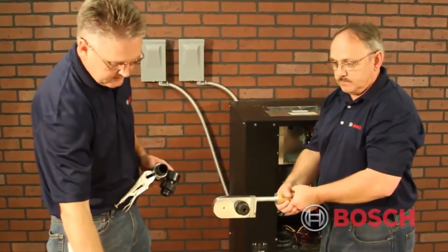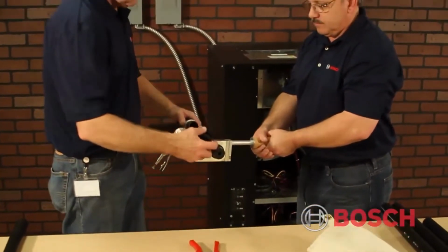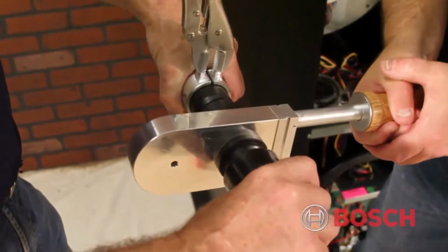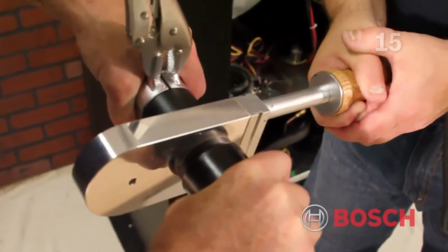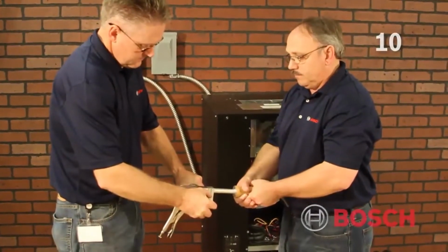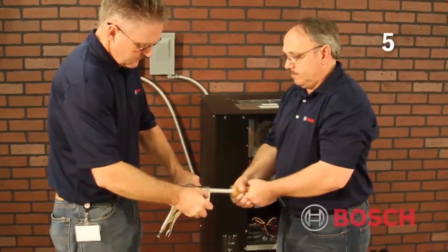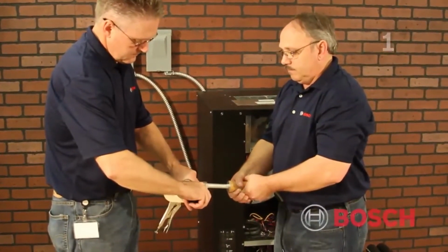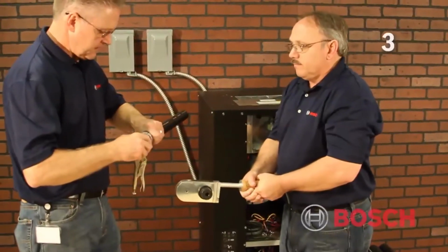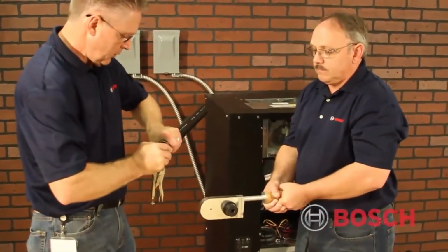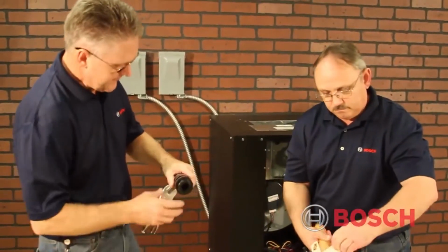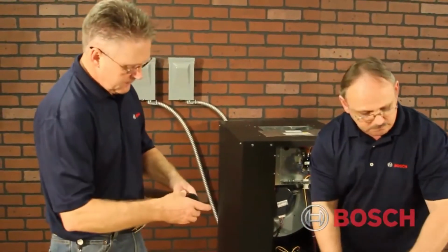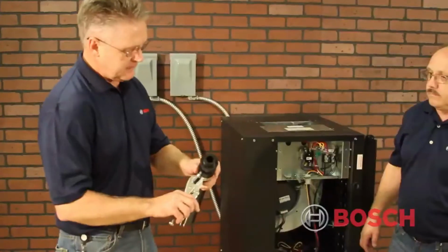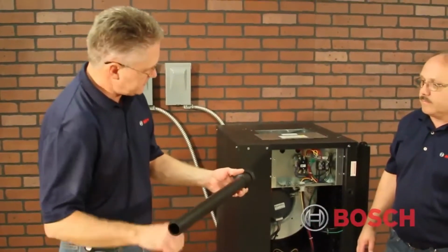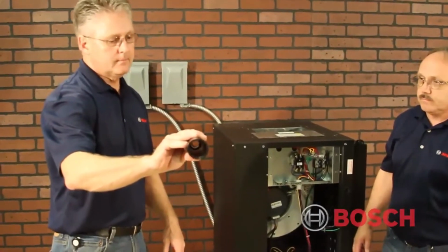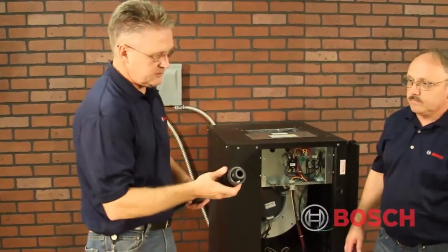This is our timer. I've got 3 seconds to put it on, and then I'm going to hold it for about 60 seconds to make sure that it sets up, and we're not going to play with it or anything like that for about 10 minutes. But that is a 1.25 inch HDPE pipe fusion. Will not leak. And that's the first one of many on this geothermal job.